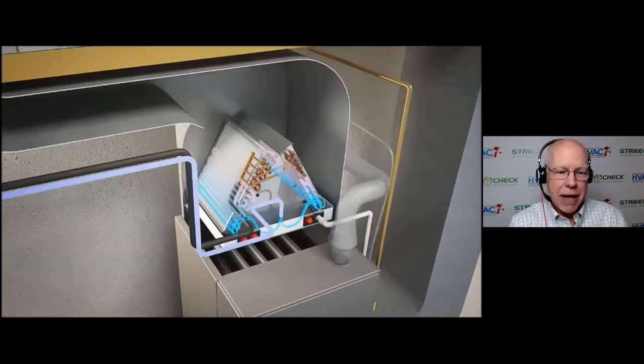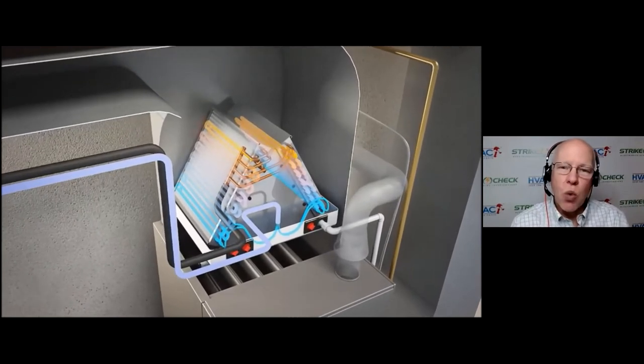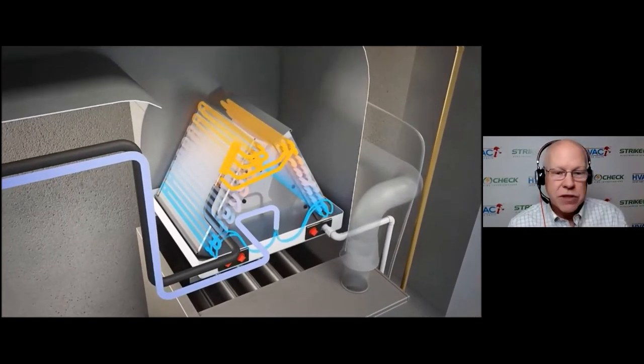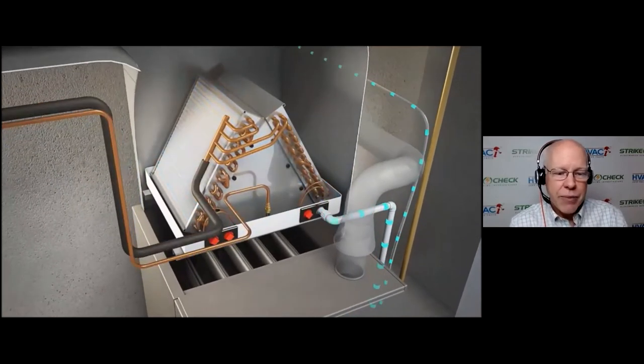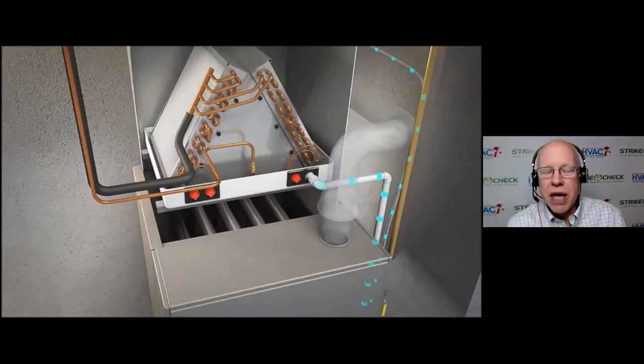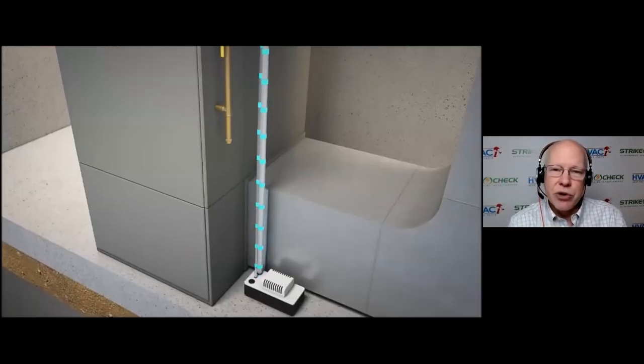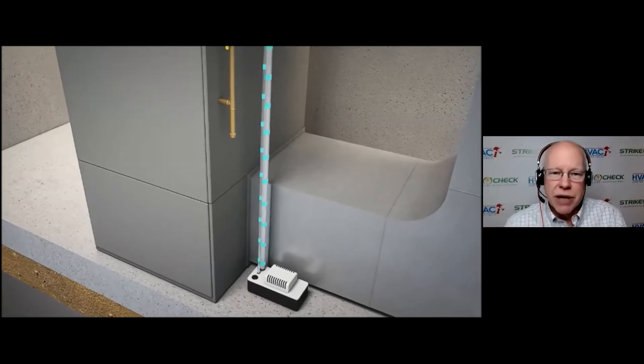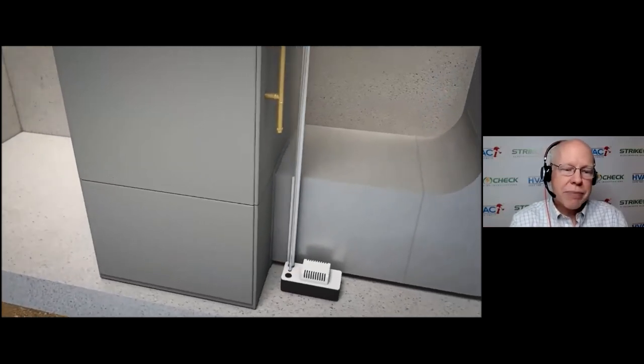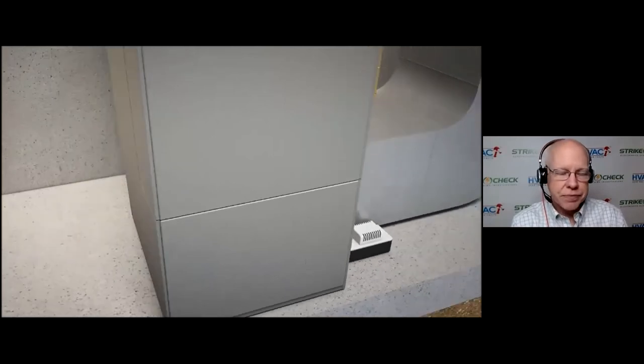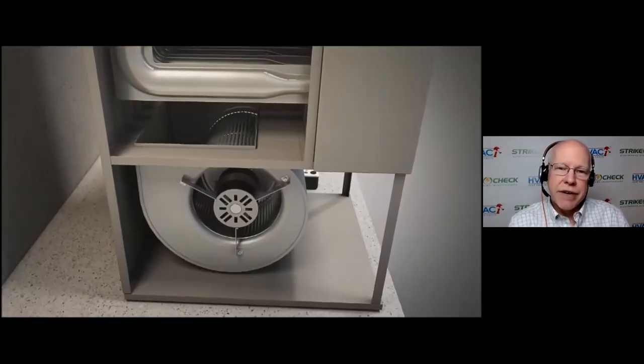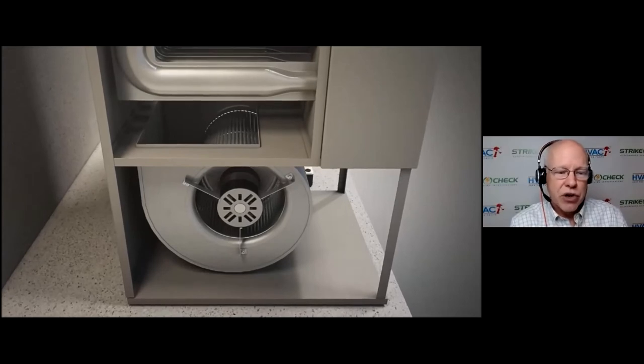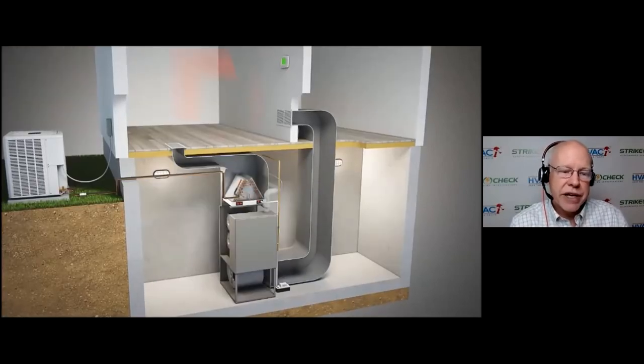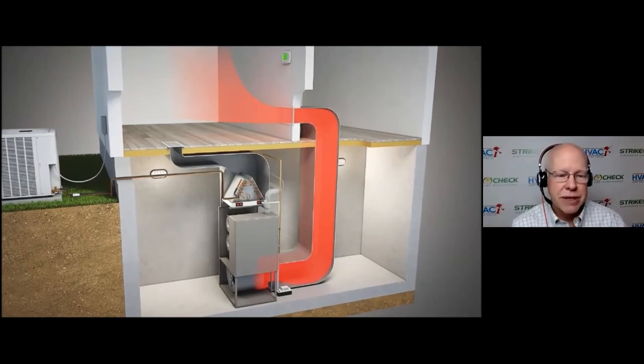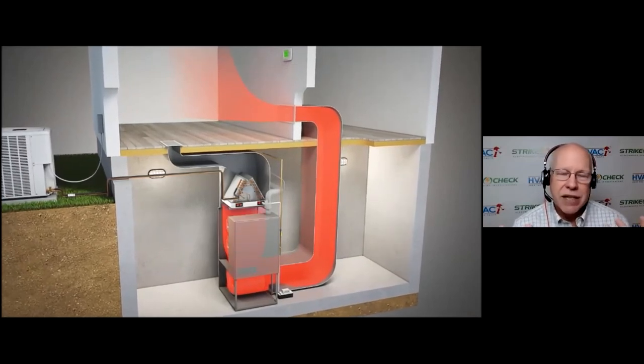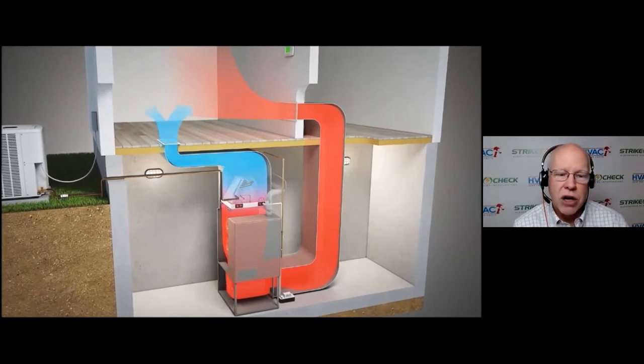So now we have a metal device that's cold and the blower's bringing warm, moist, humid air to it. The first thing that's going to happen is condensation. In our diagram, we're going to send it down to this condensate pump and pump it up and away. If you have a drain nearby, you send it into a drain. If you're in an attic, maybe you send it out to the gutter or outside the structure. As we open the system up, we see the blower down here on the bottom of this furnace, and it's pulling warm, moist air from the structure, bringing it to the evaporator coil to be conditioned. And as you can see, warm, moist air in, cool, dry air out through the supply ductwork, making our homes and ourselves feel drier and cooler and more comfortable.